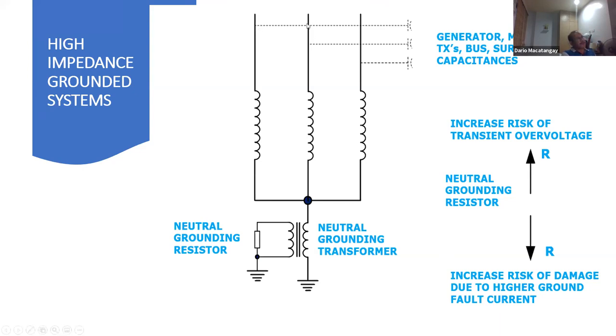Now, this is phase B, for example. So if this is phase B, this is 7,968 angle 240 volts. The third phase, which is phase C, is 7,968 angle 120 degrees volts, okay?